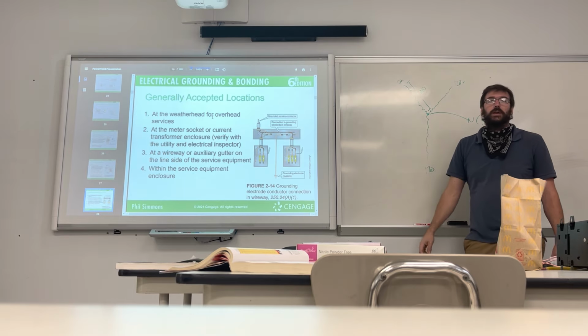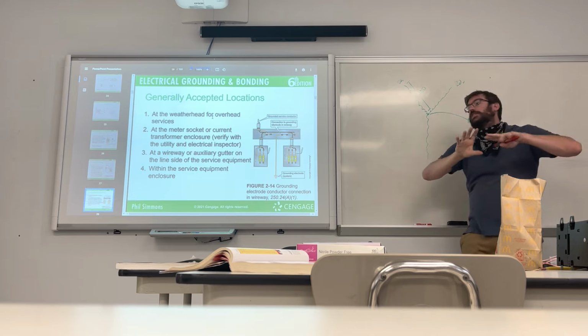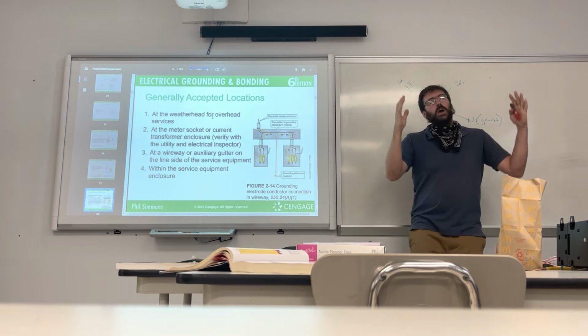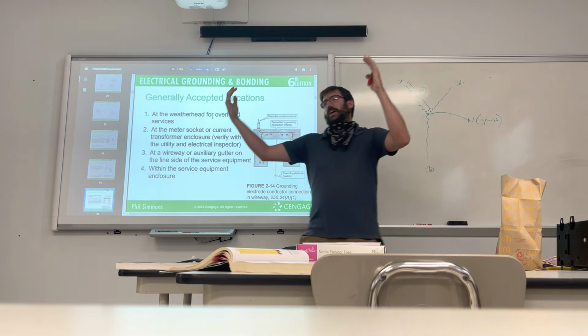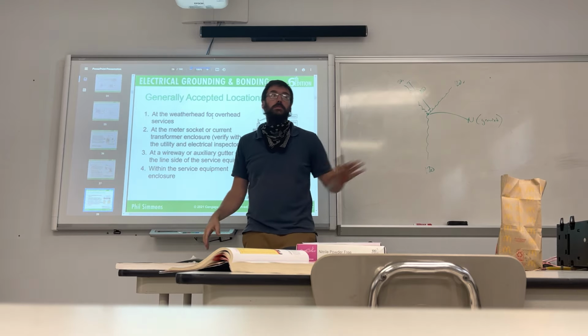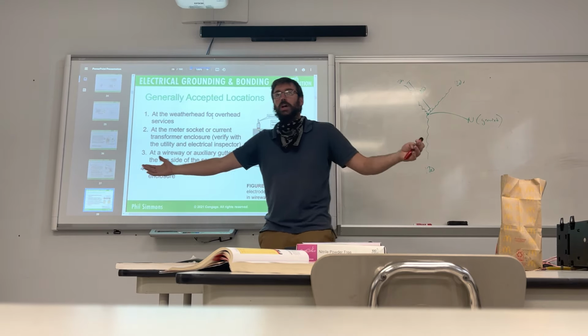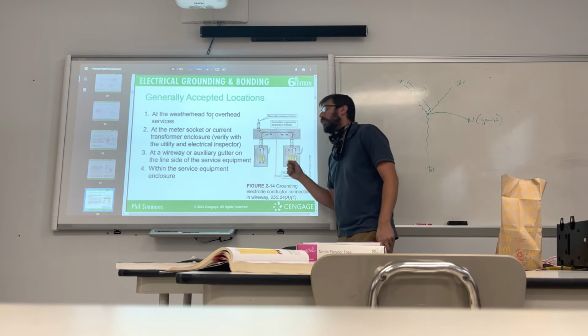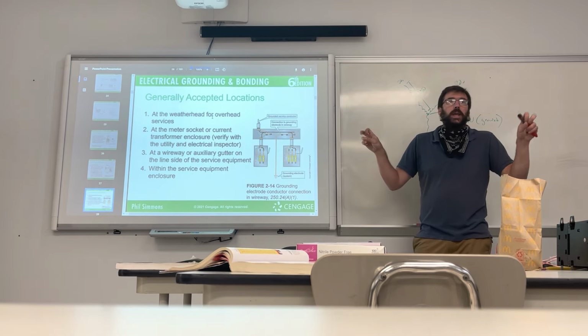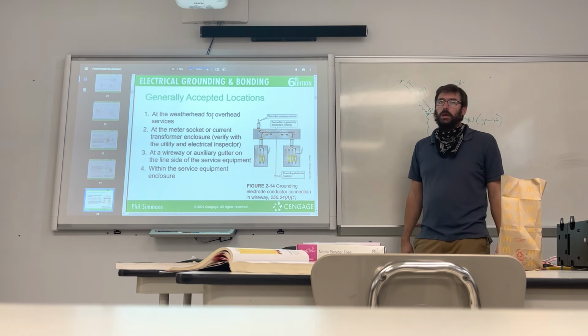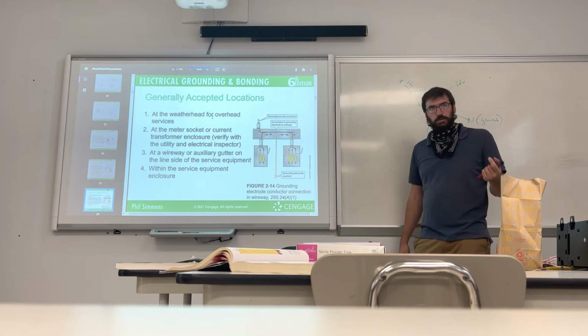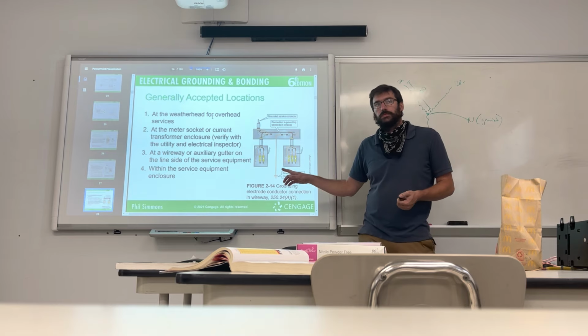So please understand that. Right off a meter, you see the meter, you see a big trunk in, and it's coming into a whole bunch of huge disconnects to feed whatever. It could feed a motor, it could feed another panel, whatever. But we're going to consider each one of these to be a main panel box or a main disconnect, which means that the bonds exist between the neutral and the ground. Any questions on this?